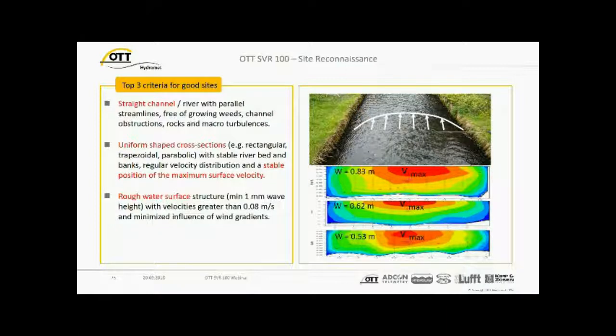And, of course, you want to have reflections from the water surface in order to get a Doppler shift. You need a rough water surface. We have very sophisticated internal electronics, so we just need a minimum of around 1 millimeter wave height on the water surface. We have done test measurements with very smooth water surfaces, and we got very good results. So you need at least 1 millimeter wave height on the water surface, even if it's not really visible to your eye. But if there's a wave on the surface, we get reflections, we get power back to the radar, and then it works. That's why the start velocity of 0.08 meters per second is very small, but it has proven to be correct.